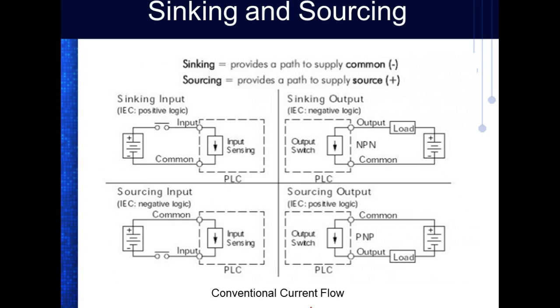And sensors are either going to be sinking or they're going to be sourcing. So that determines how you want to do your outputs. Now, if I'm running a relay, does sinking and sourcing mean anything? No. If I'm running a light bulb, does sinking, sourcing, outputs mean anything? No. All right, you understand that? Where it comes into play is if I was going to take the output of a PLC and use it as an input to another PLC, which we do a lot.